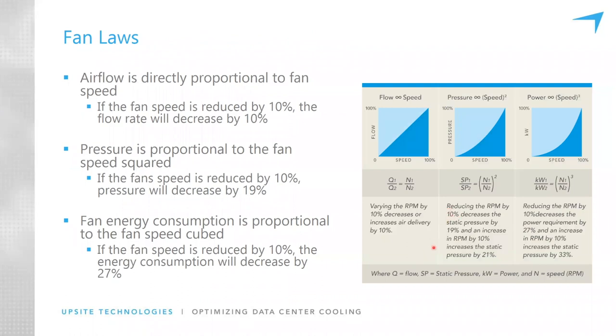So why is this so valuable to reduce the fan speeds? Well, there are the fan affinity laws. What they show us is that the fan speed is proportional to the flow rate, so if we reduce the fan speed by half, we get half the flow. The pressure is proportional to the square of the fan speed, so if we reduce the RPM of the fans by 10%, that's a 19% reduction in the static pressure. And the power consumed is proportional to the cube of the fan speed, so if we reduce the fan speed by 10%, it's a 27% reduction in the power required by the fans.